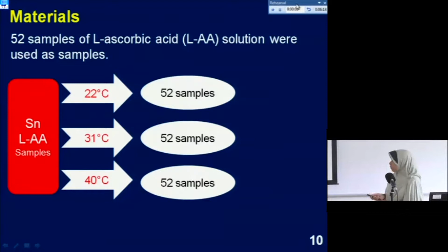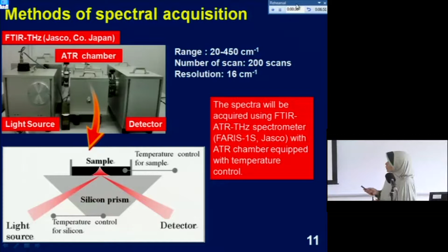These are the methods of spectral acquisition. First, I put the sample on the surface of a silicon prism, and when the terahertz wave comes to the silicon prism, some of the light will be reflected back into the sample and generate the evanescent wave. This evanescent wave will penetrate the sample with a penetration depth depending on the wavelength. And then the spectra of the sample containing the information will be detected by the detector. These are the parameters used in our study.